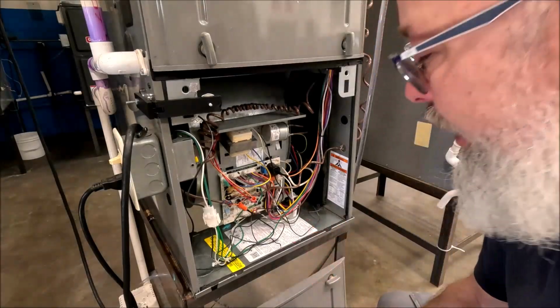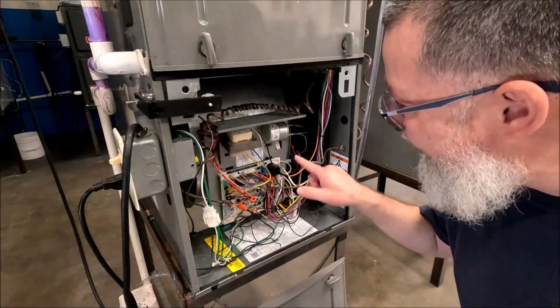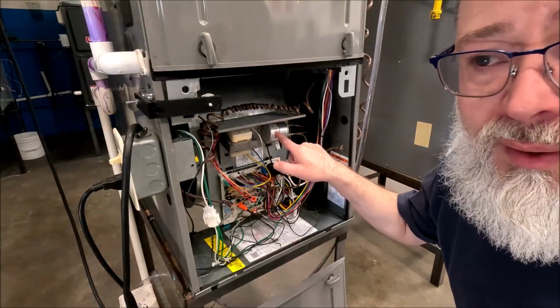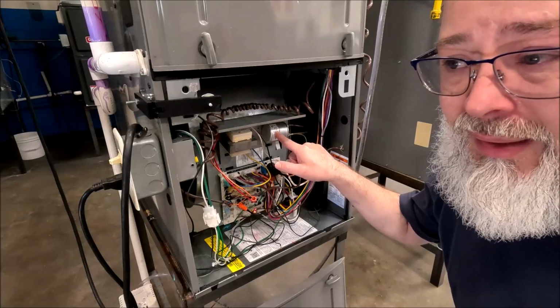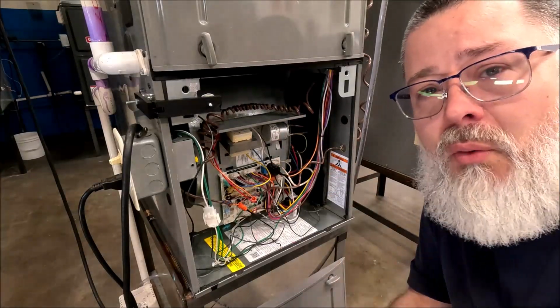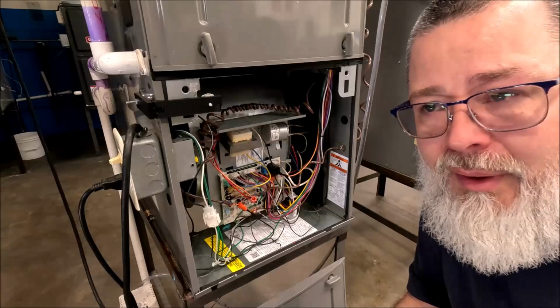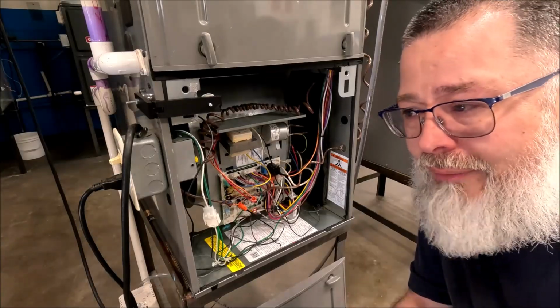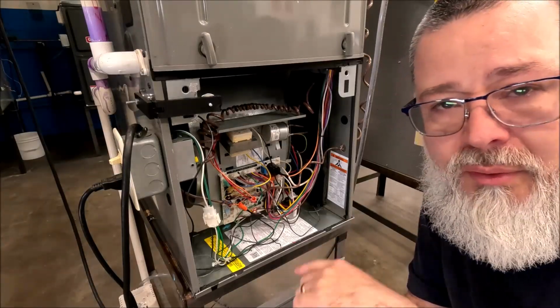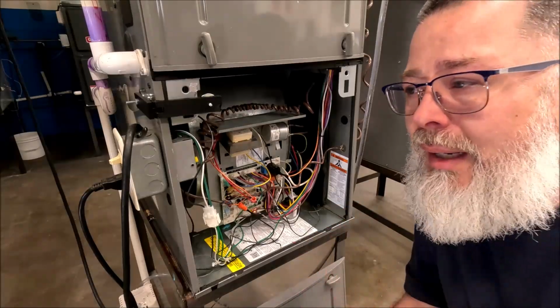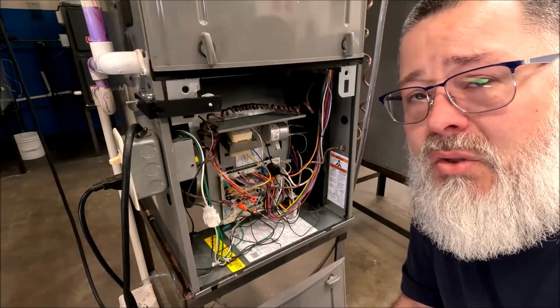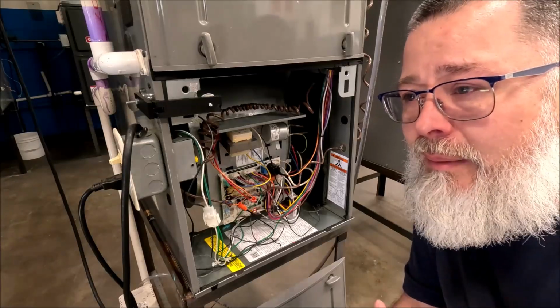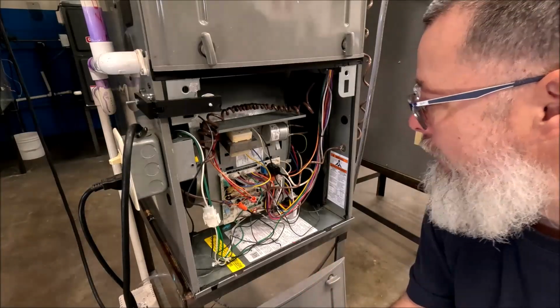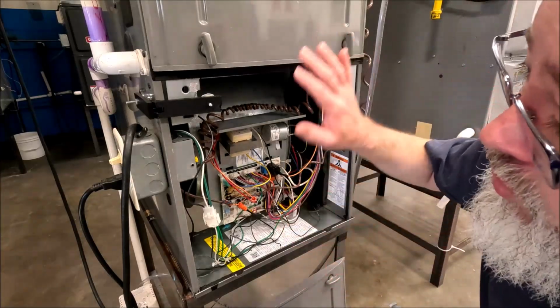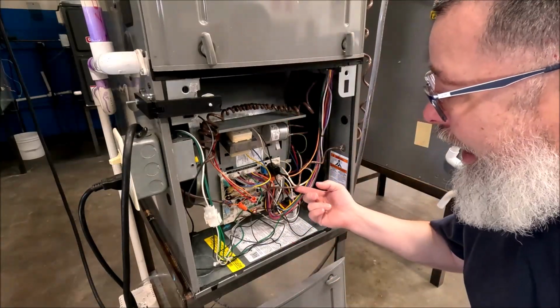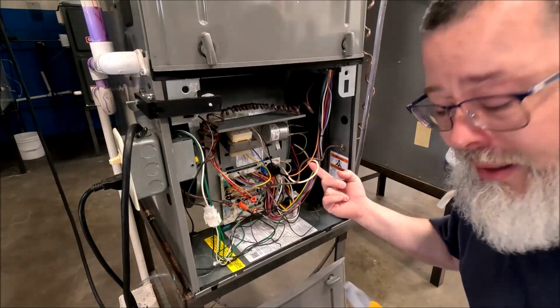So with this blower motor, it's not an X13 style. I can look right here and I see the capacitor for it. So that means it's a PSC motor. And I know that capacitors are always on the start winding. Anytime I'm looking at a diagram and I see a capacitor, whatever winding of that motor is going to, whether it's a fan motor or a compressor, I know that that's going to be the start winding. And for me, that means something.